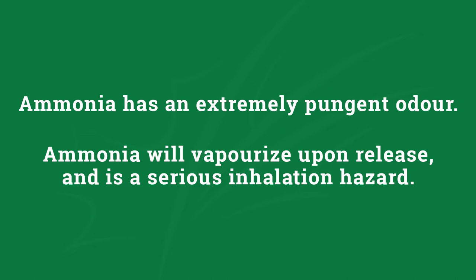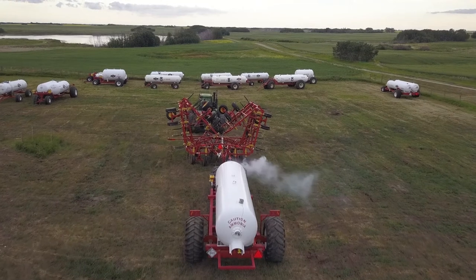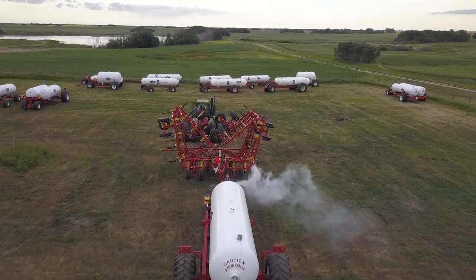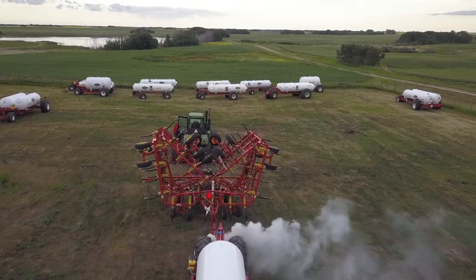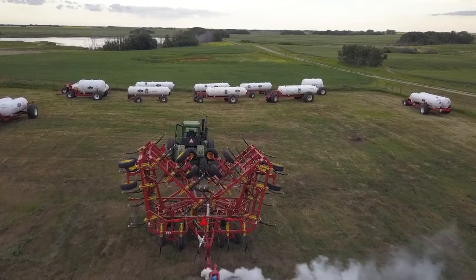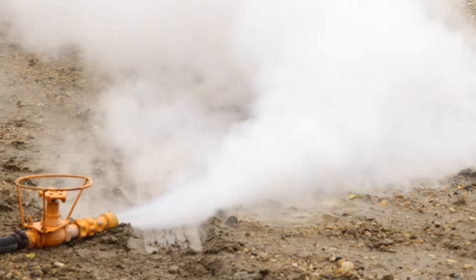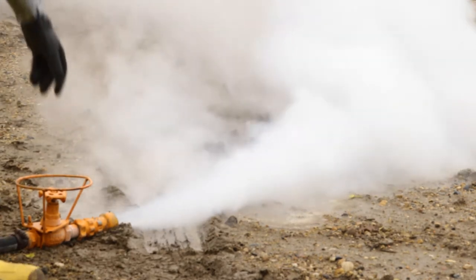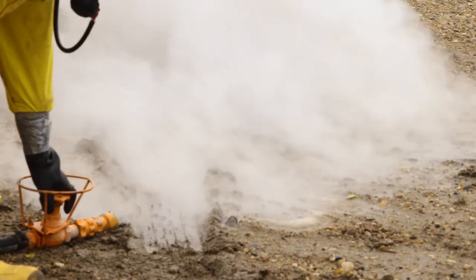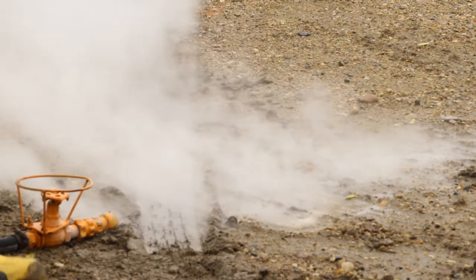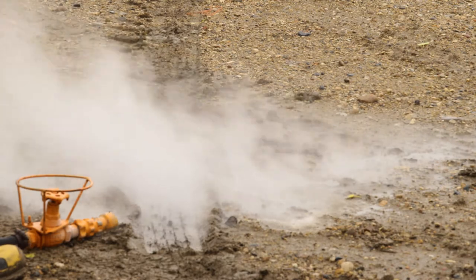An anhydrous ammonia plume may also be seen if the humidity is high enough, because it draws moisture from the air. If anhydrous ammonia escapes from its containment, it turns immediately into a gas and blows with the wind as it dissipates. However, this is not true if the temperature is below minus 28 degrees Fahrenheit or minus 33 degrees Celsius — it may form a white plume or it may be invisible. You must act on the assumption that there is ammonia gas or vapor downwind of a release.